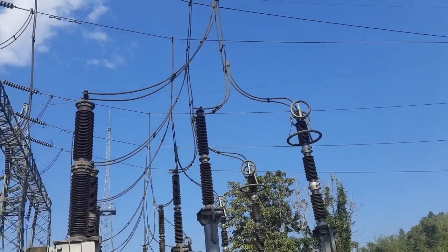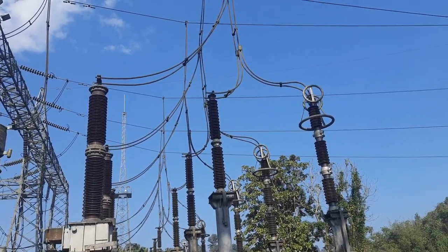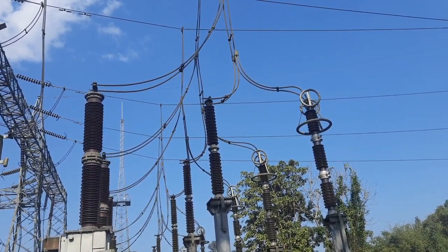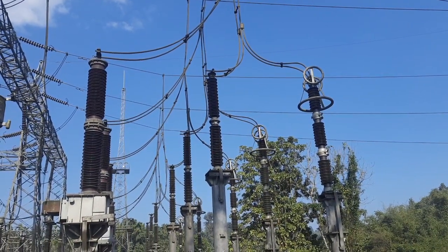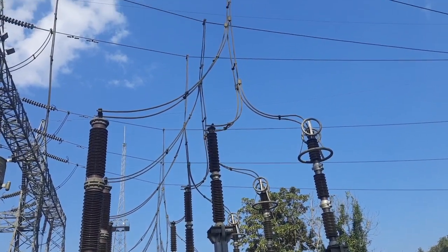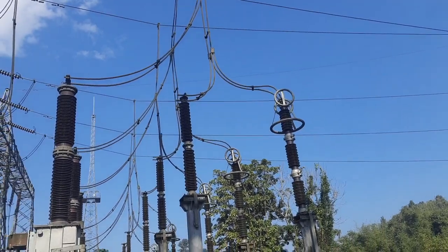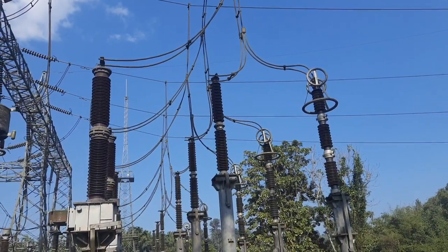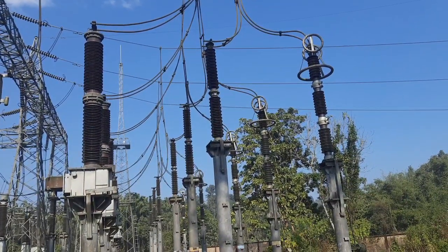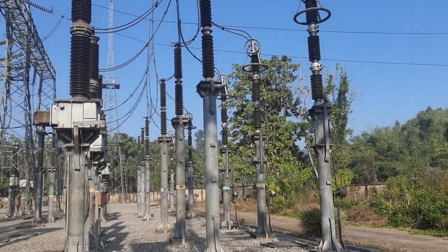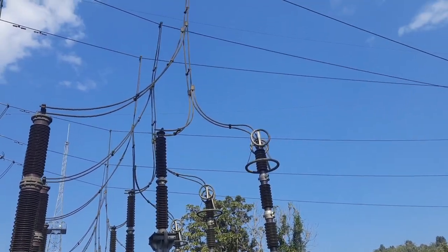And then the second one that you see here is just a support structure. If it is there or not there also, that doesn't matter electrically. People may ask why we're using this, but it is just for easy maintenance. For example, if you have to disconnect, remove or replace the surge arresters, without this support it will be difficult, so this is provided. It is called a bay post support, BPS. It is there in the middle and has significance in case of maintenance activity.